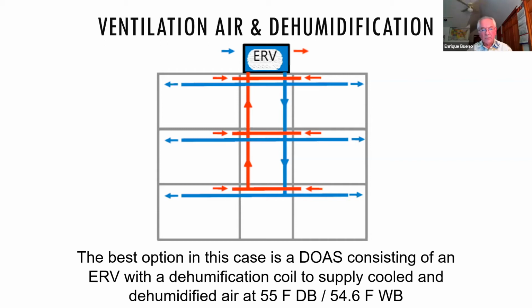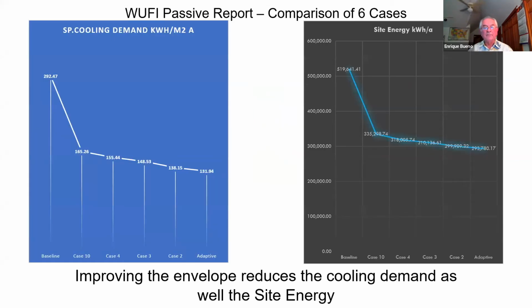The best option that we found for ventilation was DOAS, centralized on the roof, consisting of an ERV with a dehumidification coil to supply cool and dehumidified air at 55 Fahrenheit or 54.6 wet bulb. Each apartment will also have its own cooling-only mini split. But depending on what we experience in the single family homes with the Minotair, we may change the DOAS for decentralized ventilation with Minotair, since this unit has been implemented already in many large multifamily projects here in the United States.